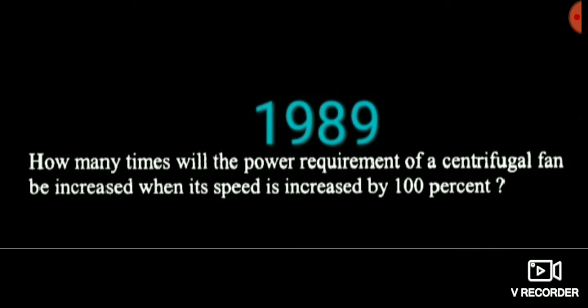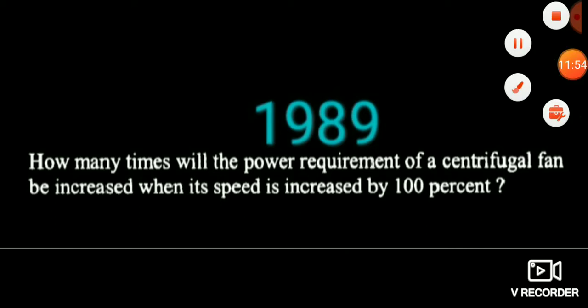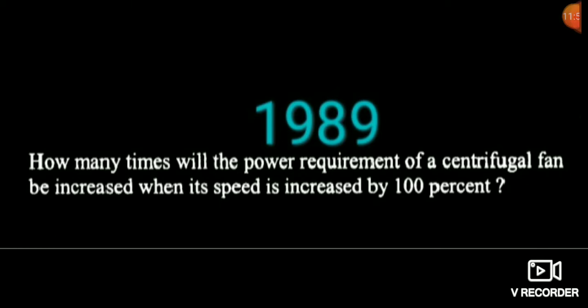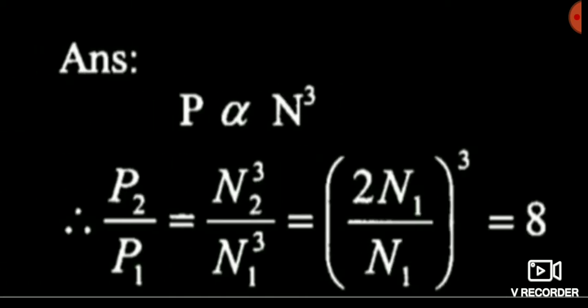The 1989 question: how many times does the power requirement of a centrifugal fan increase when its speed is increased by 100 percent? Power is directly proportional to N cubed. Speed increased by 100% means speed becomes 200 from 100 — that is 2 times. So 2 to the power 3 equals 8. The answer is 8 times.